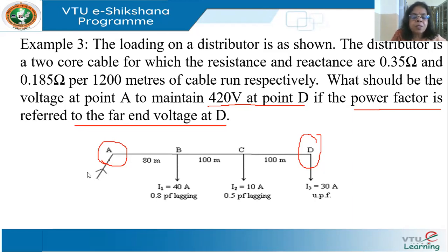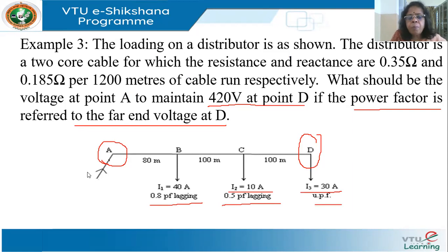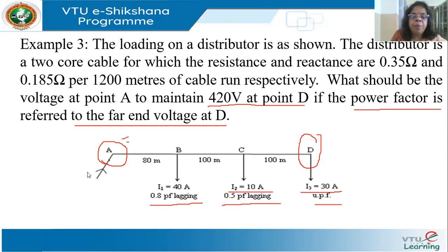Now look at the three loads: 40 amperes at 0.8 pf lagging, 10 amperes at 0.5 pf lagging, and 30 amperes at unity pf. This is a simple problem — can you get the approach? The first thing is you draw the figure. I want to calculate VA, which will essentially be VD — the receiving end voltage — plus the total drop in the line.